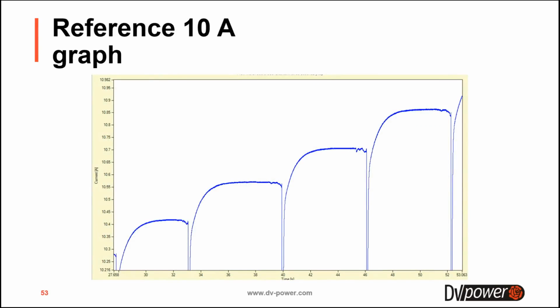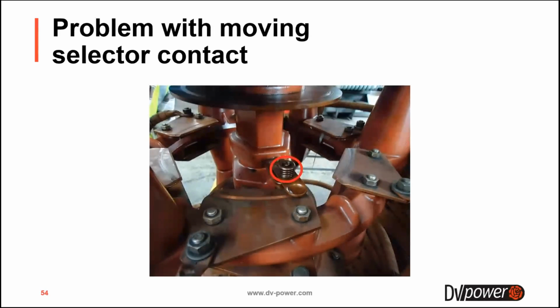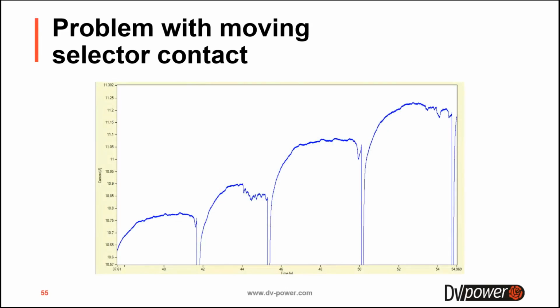What we first did is we took a reference graph with 10 amps when everything was in good condition. Then we simulated a problem with the moving selector contact by losing this spring, which is marked with a red circle. We can see that during every transition we have a problem on the static part of the graph. Even before the moving contact leaves the stationary contact, we have disturbances, which means we have increased or unstable resistance. In this case, the unstable resistance was caused by bad contact, obtained by losing the spring that pushes the moving contact to the stationary contact here.